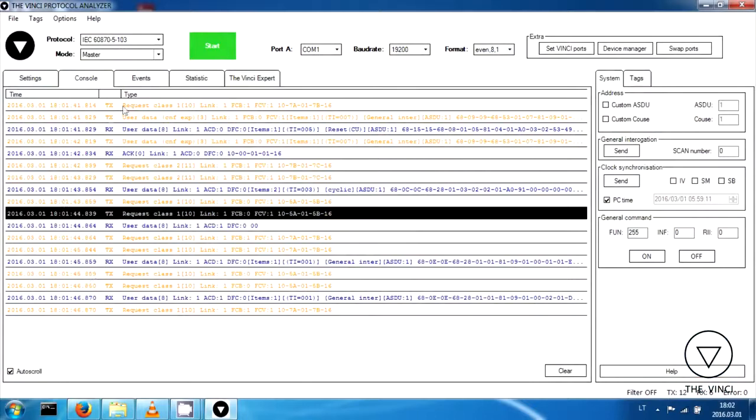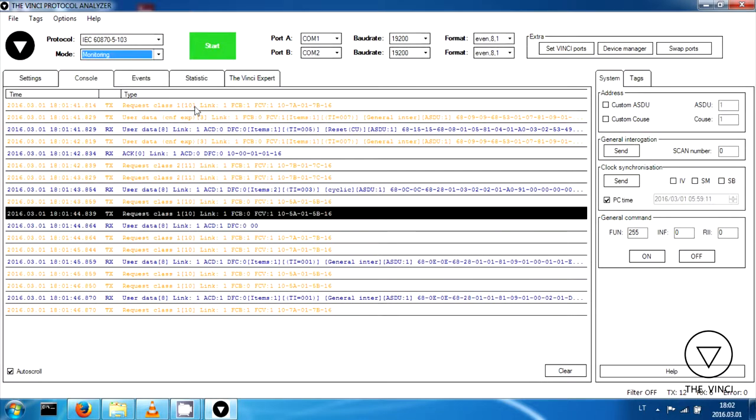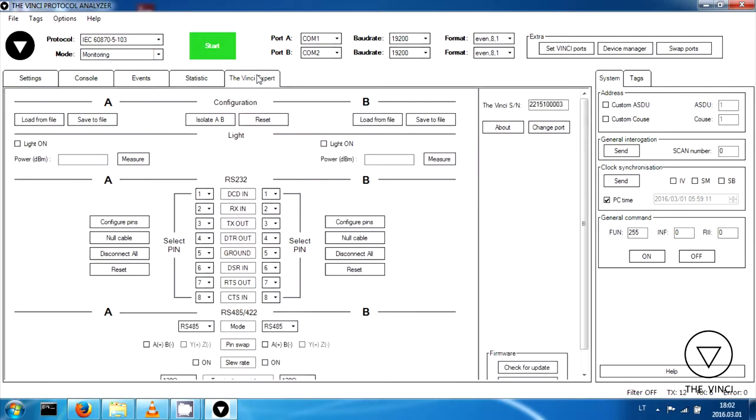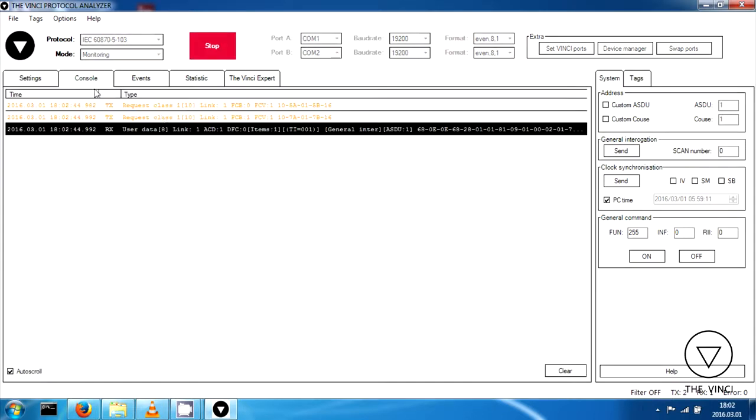And I will show you now what is done on software. I'm already stopped master. So in order to see what is going on between these two interfaces, we can change to monitor. So we select second port. The baud rate is the same. And also we need to change RS232 pins. Because on RTU560, RS232 is on 2, 3 and 5.